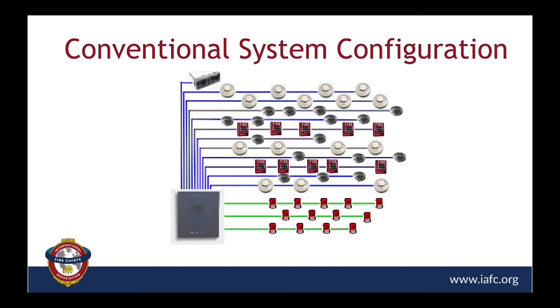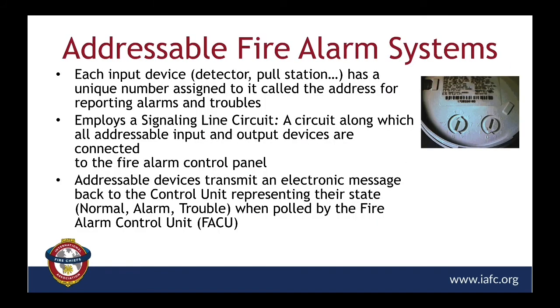Okay, that makes sense, just how you described it. So there could be a series of detectors or a series of pull stations, and they'd have to look to see which one's activated. Right. Great. We know that a smoke detector is activated because it'll have a solid light on it. A little LED will light up on that detector to say, I'm the one that activated. In the case of a manual pull station, as Richard mentioned, they have to be key reset. When you pull down a lever or push down the pull station, it remains locked in that open position, which will give you the visual indication that it has gone off.